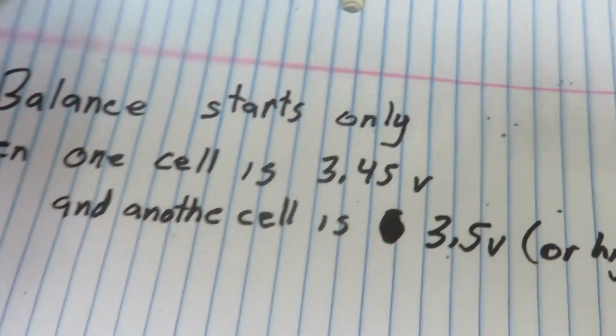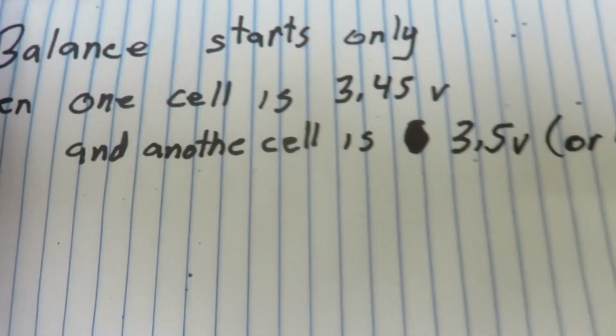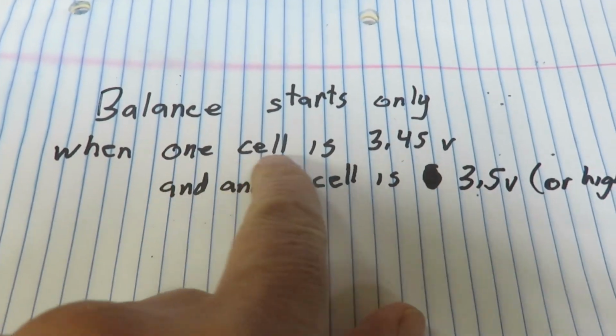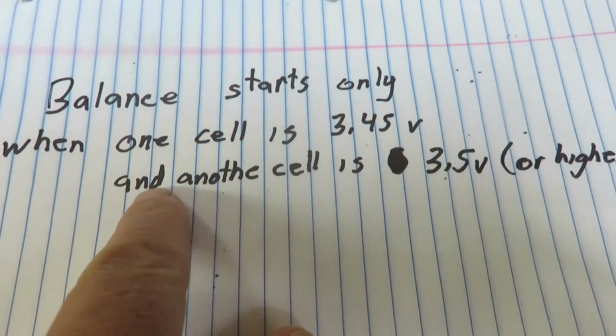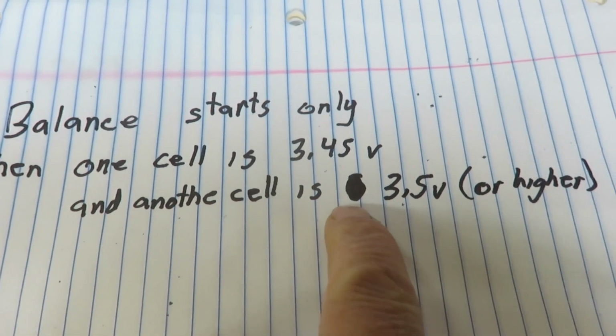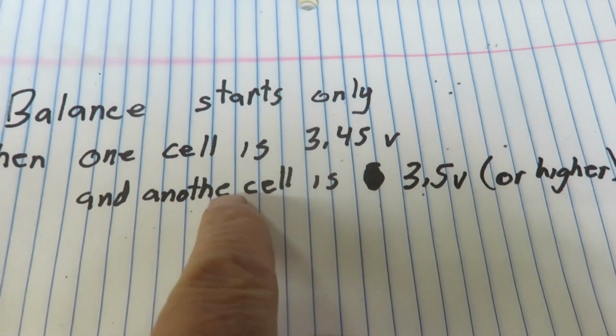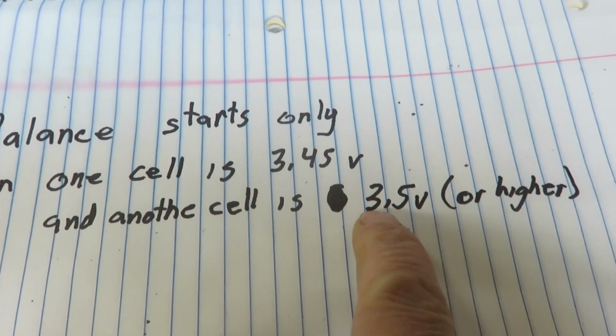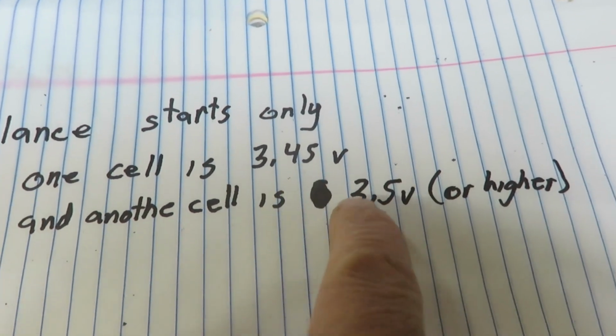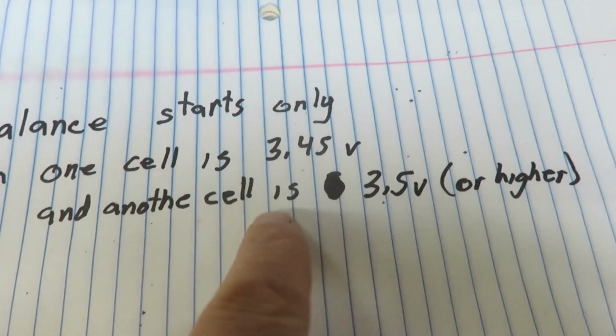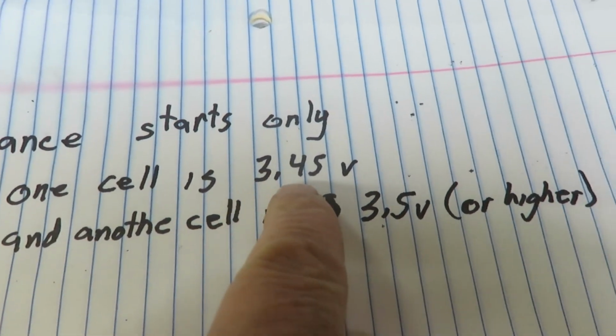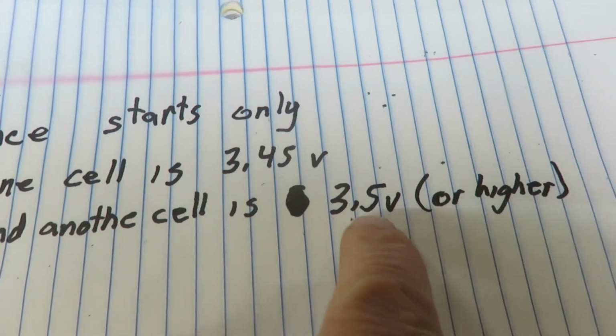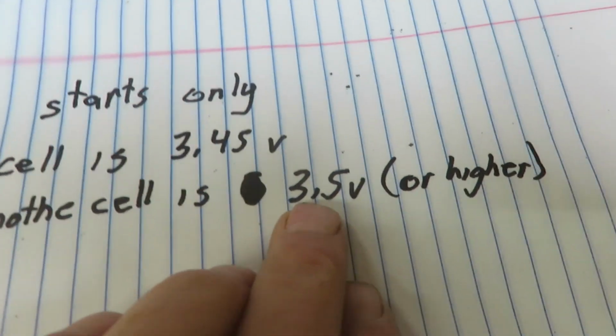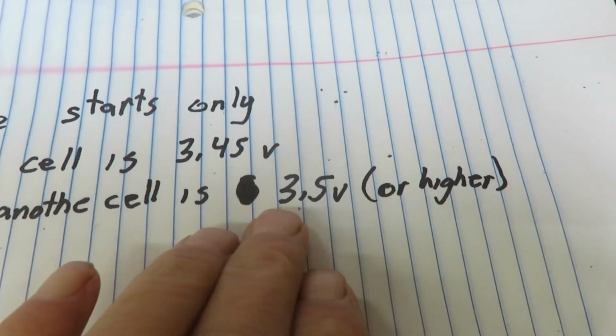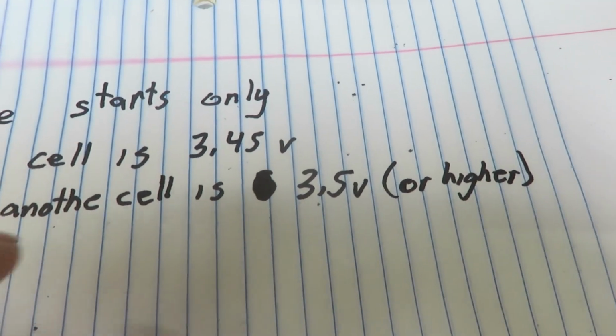Oh, that was the balancing. The balancing only starts when one cell is 3.45 volts and another cell has to be at least 3.45 volts plus 50 millivolts higher, or it's not going to balance anything. So if another cell is 3.49 volts, there's no balancing going on. It has to be 50 millivolts more for one cell or more cells.